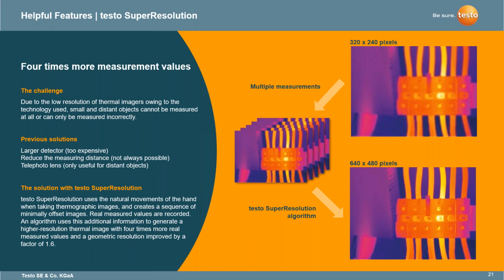In thermal imaging, we want to make sure we have a very crisp image as well as having the right scale set, so that we get everything we need to do a general analysis of what we're inspecting. With that inspection, we want to make sure we're reporting it and presenting it to the customers, showing a potential anomaly with this image or this specific component. This is an algorithm that takes additional information to generate a higher resolution thermal image with 4 times more real measured values and a geometric resolution improved by a factor of 1.6.